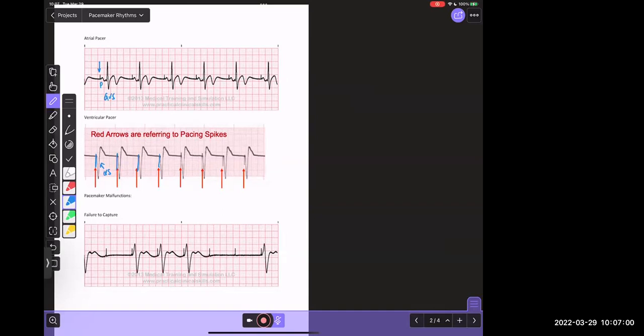All right. So with that in mind, let's now talk about some of the problems we can run into with pacemakers, what we call malfunctions. The first problem I want to talk about is called failure to capture. Failure to capture means that the pacemaker is sensing, and it is firing, but it is not causing electrical capture. So what you will get is pacer spikes without QRS complexes. You see a pacer spike there and no QRS complex. And then you do have a pacer spike and a QRS, pacer spike QRS, pacer spike QRS.